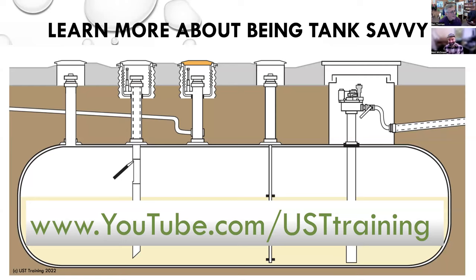Ben, can you speak for the need of having an electronic line leak detector properly set up? Vicky's from Wisconsin. I did a tank inspection years ago in Wisconsin. They had 300 feet of pipe. The tank was here and the piping was way across the property over there. It turns out that the leak detector was only certified for 150 feet of pipe length.